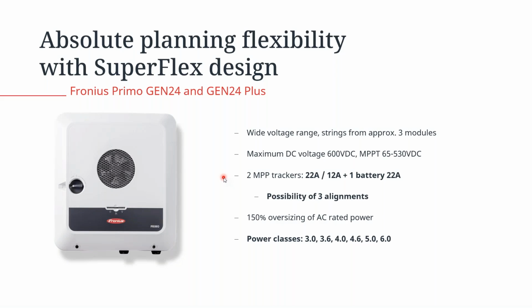Let's talk about the inverter features of the Gen24 inverter. So the Gen24 inverter, both the Symo and PRIMO versions of it, are designed to offer you absolute planning flexibility, starting off with what we refer to as the SuperFlex design. So in terms of analyzing what these SuperFlex design capabilities are, we are talking about the possibility, for instance, to start with a wide voltage range for input on the DC side. And this means that you can design your PV array starting with 3 modules.